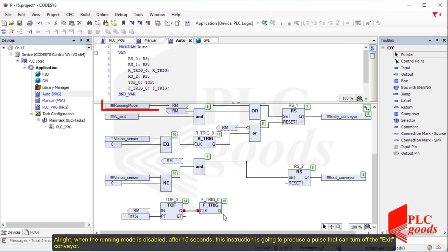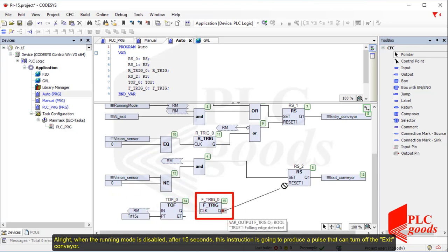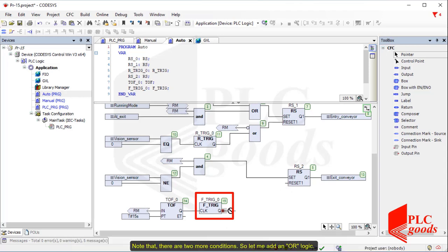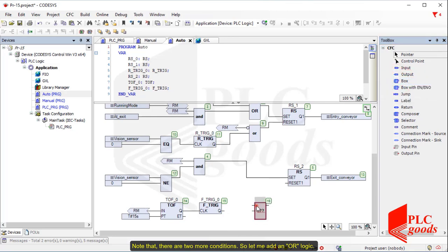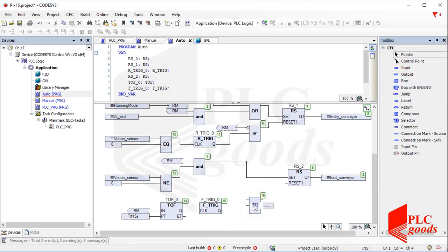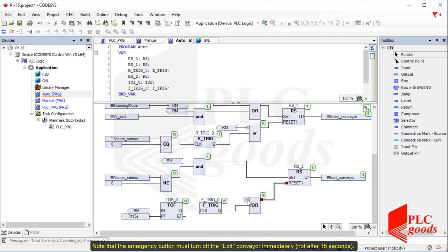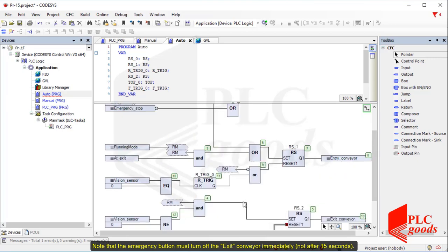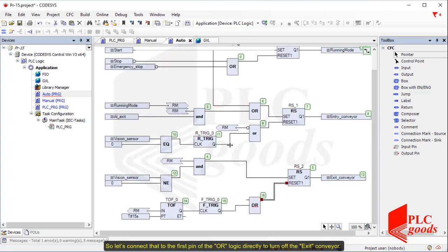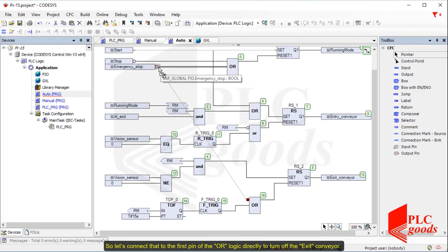Now I need to specify the conditions that turn off the exit conveyor. Note that after pressing the stop push button, the exit conveyor remains on for 15 seconds. Therefore, I need an off-delay timer. When the running mode is disabled, after 15 seconds this instruction is going to produce a pulse that can turn off the exit conveyor. Note that there are two more conditions, so let me add an OR logic. The emergency button must turn off the exit conveyor immediately, not after 15 seconds, so let's connect that to the first pin of the OR logic directly.